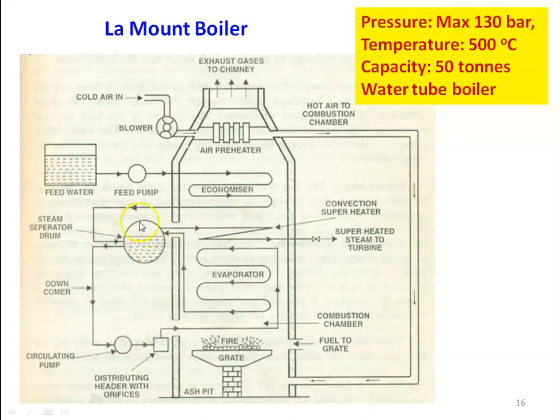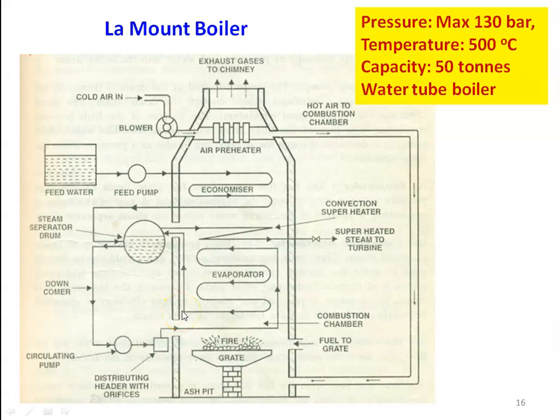Then we have the steam separating drum. Water enters here and is taken to the circulating pump and then to the distribution header. From here the water is circulated through the evaporator using the circulating pump, where it absorbs heat energy, converts into steam, and the steam returns to the drum. In the steam separating drum, steam collects at the top. When the steam stop valve is opened, the steam flows through the superheater where it is superheated, and the superheated steam goes to the steam turbine or steam engine.